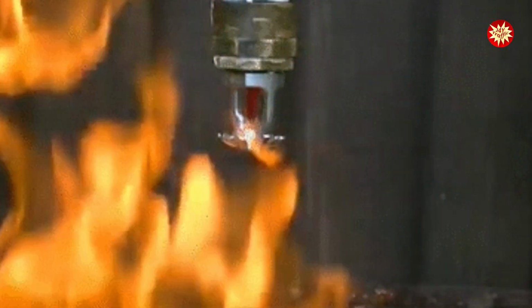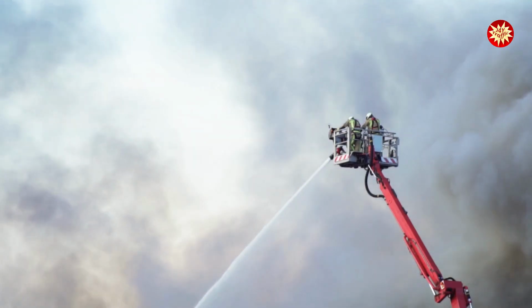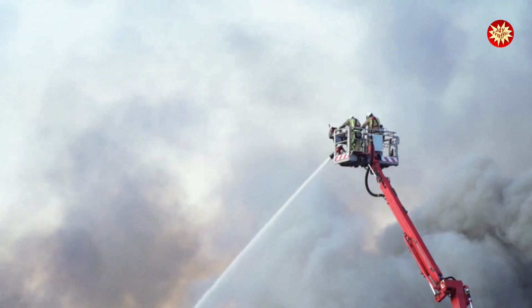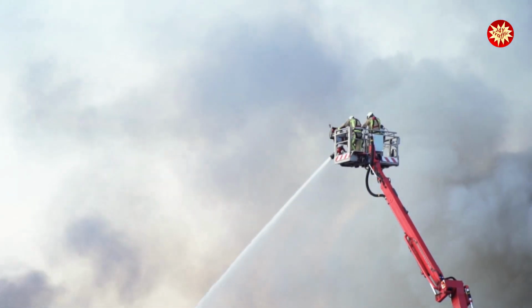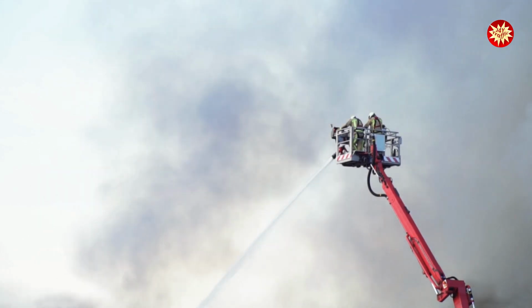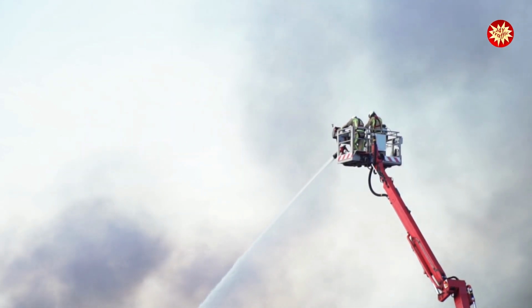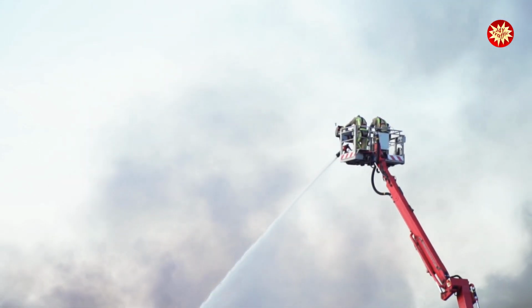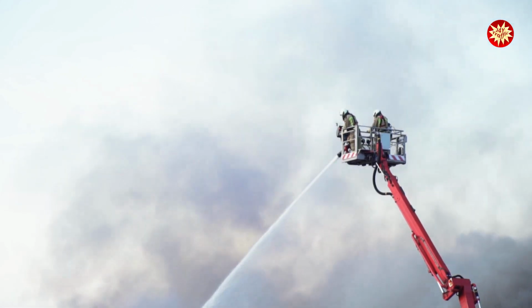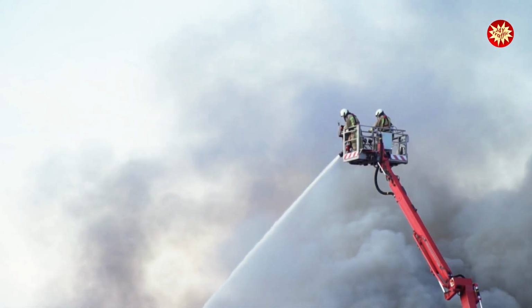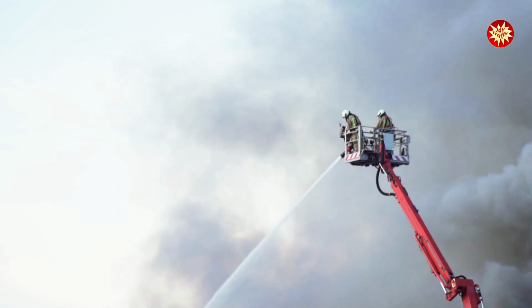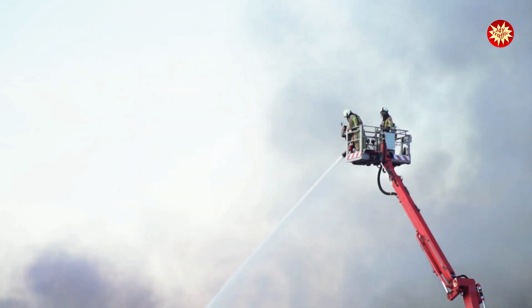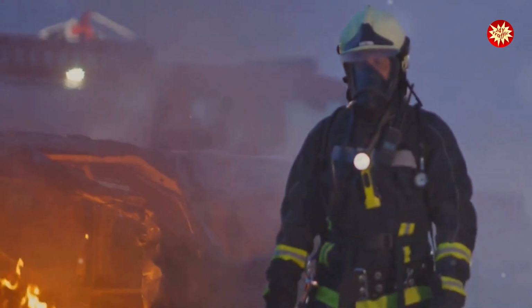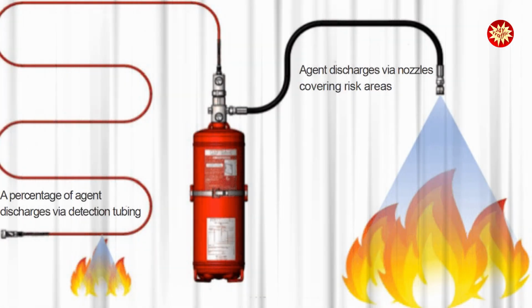Contrary to popular belief, sprinkler systems are not triggered by smoke. This ensures that they activate only when there's an actual fire, preventing accidental discharges. When a sprinkler head is activated, it releases a jet of water, targeting the source of the fire. Sprinkler systems are designed to control fires, not necessarily extinguish them completely. Their primary goal is to suppress the fire, preventing it from spreading and giving occupants time to evacuate and firefighters time to arrive.